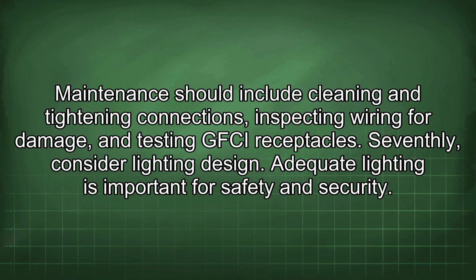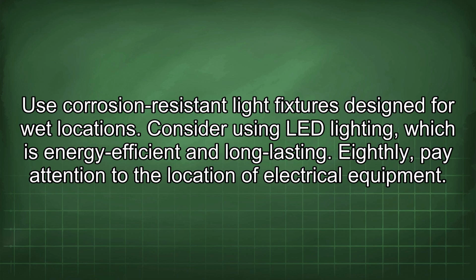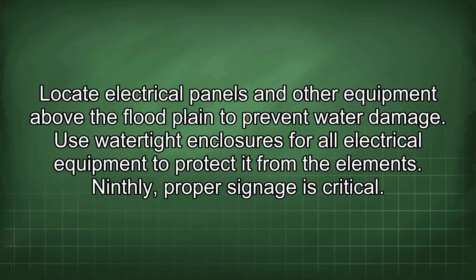Seventhly, consider lighting design. Adequate lighting is important for safety and security. Use corrosion-resistant light fixtures designed for wet locations. Consider using LED lighting, which is energy efficient and long-lasting. Eighthly, pay attention to the location of electrical equipment. Locate electrical panels and other equipment above the floodplain to prevent water damage. Use watertight enclosures for all electrical equipment to protect it from the elements.